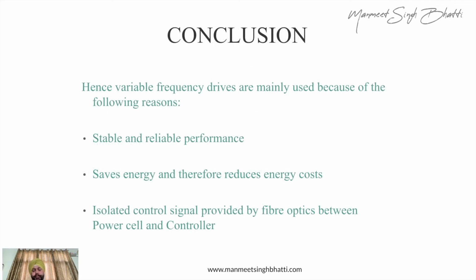The conclusions, it's pretty simple, that you must have understood now. The first thing, that once you are putting a VFD, is actually giving you a stable and reliable performance of your power quality. So the kind of voltage surges which happen in the systems, the kind of breakdowns that happen in the system, the motors have to face everything. Once you put a VFD in between, the VFD becomes a kind of protecting device also, because it's controlling the power. So anything wrong that happens, it happens to the VFD. It never gets passed on to your motors. So your motors, which are bigger ones, which are costly ones, actually don't have to bear the brunt of the power quality. So most of the quality issues which are in the power are actually taken care of by the VFD. So VFD gives you the required quality of power to your motor.